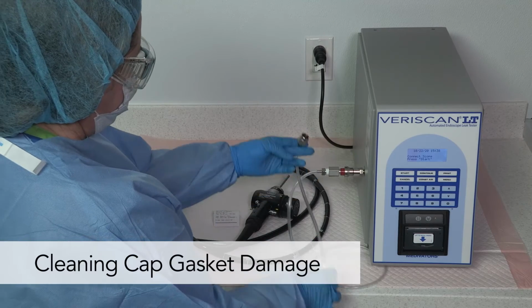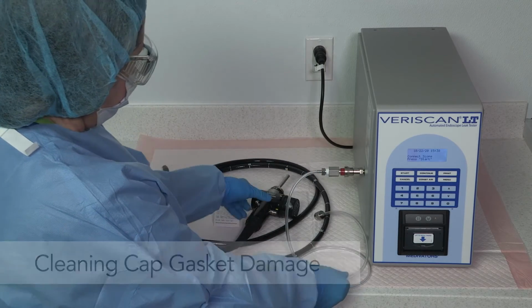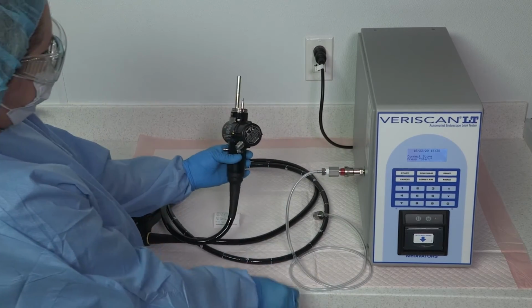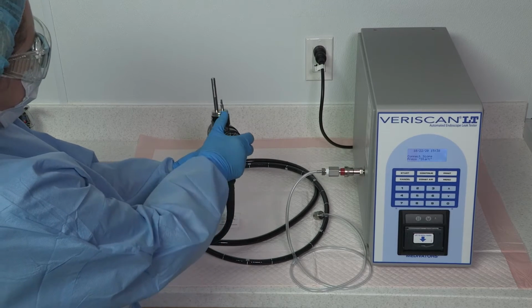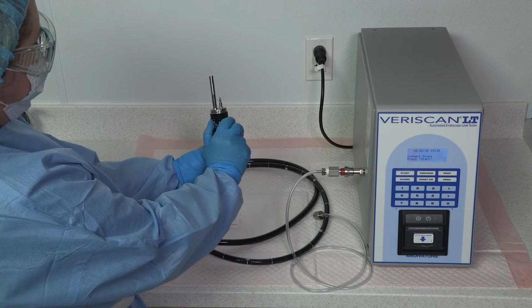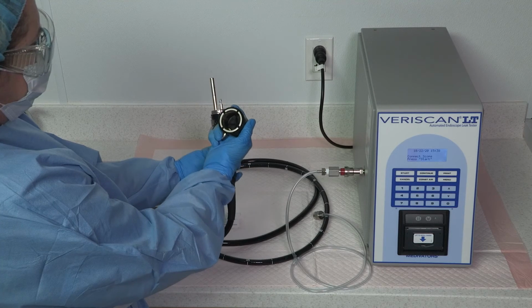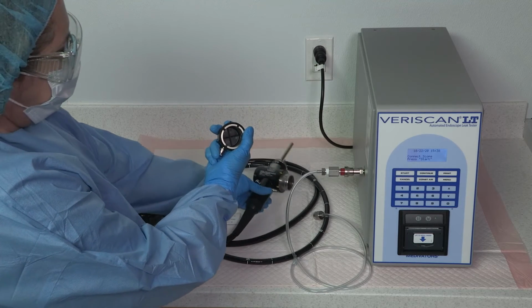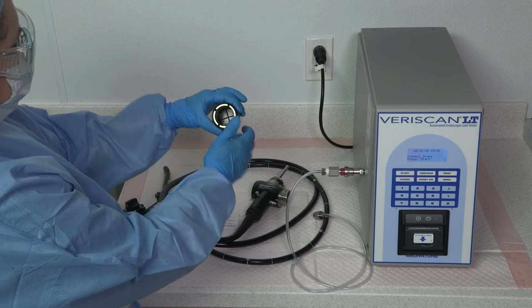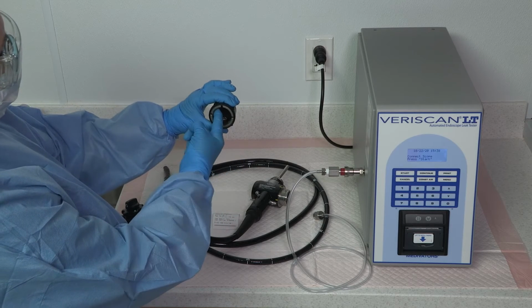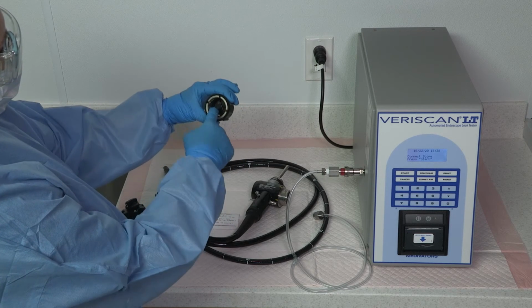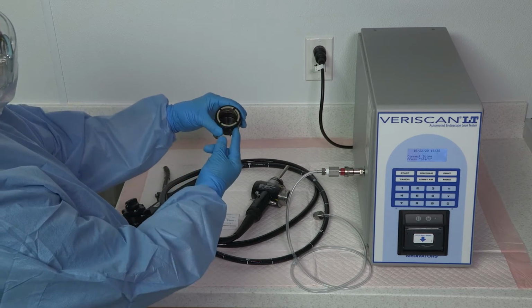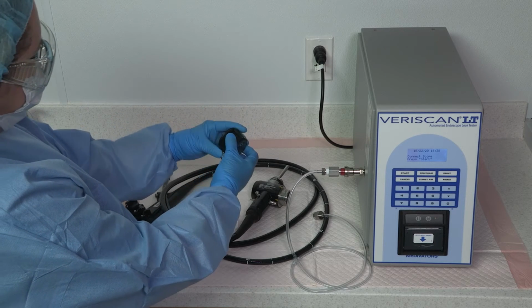Some endoscopes are equipped with a water-resistant cap. If the rubber seal or gasket on the inside of the water-resistant cap is damaged, a false fail leak test result can occur. Remove the water-resistant cap from the endoscope and inspect the cap for wear, damage, or corrosion. Inspect the O-ring for rips or tears. If the rubber sealing area is not in perfect condition, replace the water-resistant cap with a new one.